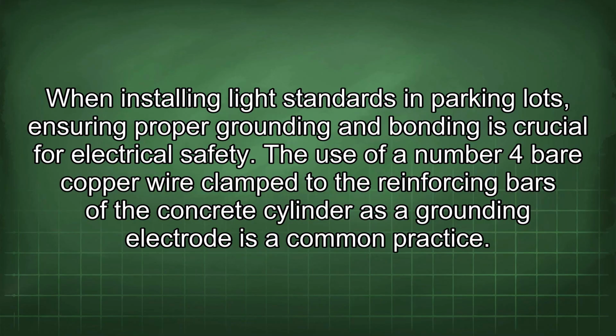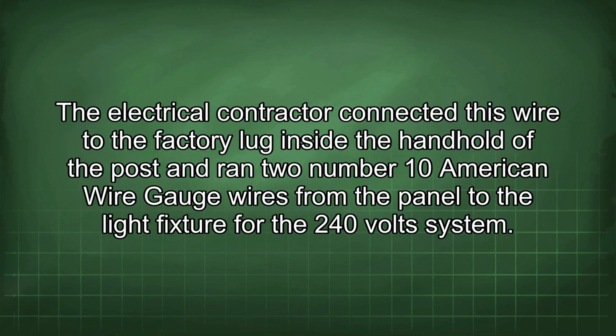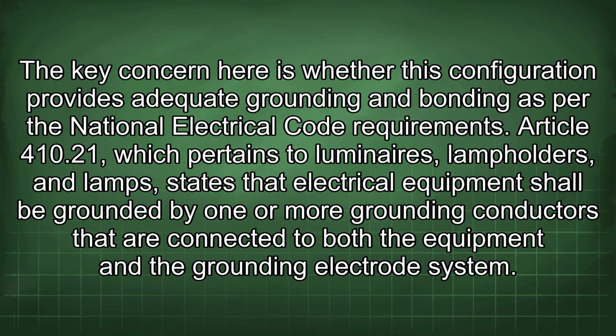When installing light standards in parking lots, ensuring proper grounding and bonding is crucial for electrical safety. The use of a number 4 bare copper wire clamped to the reinforcing bars of the concrete cylinder as a grounding electrode is a common practice. The electrical contractor connected this wire to the factory lug inside the handhold of the post and ran 2 number 10 American wire gauge wires from the panel to the light fixture for the 240-volt system. The key concern here is whether this configuration provides adequate grounding and bonding as per the National Electrical Code requirements.